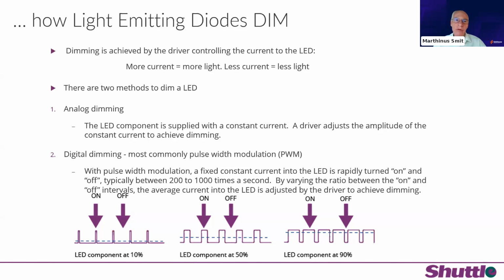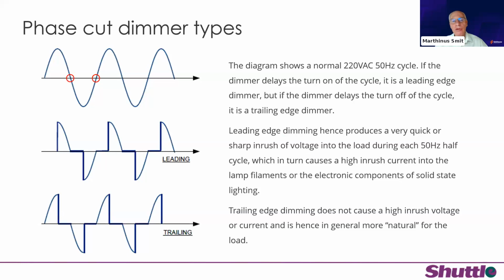This type of dimming is reserved mainly for your external drivers, because it requires much more electronic components. It's much more difficult. It is much more accurate. It provides you with a very, very low dimming, and typically more robustness against fluctuating supply voltages. There are some disadvantages, and you find that some of the high-end drivers, especially from your traditional European manufacturers, actually combine analog and digital dimming in certain cases. Now, because we concentrate on phase cut dimmers today, just a quick introduction here.